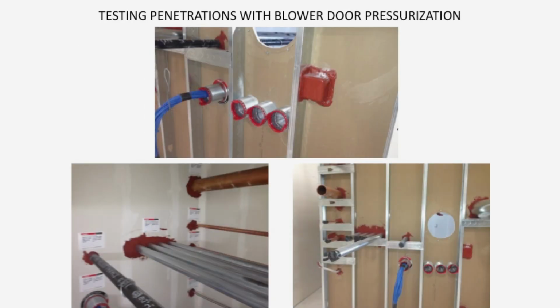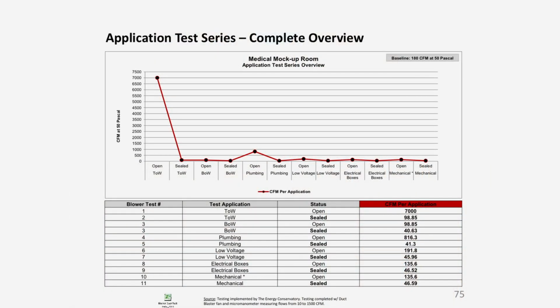So in the next slide you see a whole bunch of seals on a variety of things that come through the wall. If we did not pay attention to sealing these, we would not have control in those rooms, even with the ceiling tile in, because of how many penetrations and utility boxes there are in a patient room, especially in ICU. In the testing penetrations slide, you see a wrap around one of the electrical boxes instead of the mud I was putting around previously. We tested every one of those openings, and we could demonstrate a significant decrease in escaping air with each one of those gadgets, open and then closed.